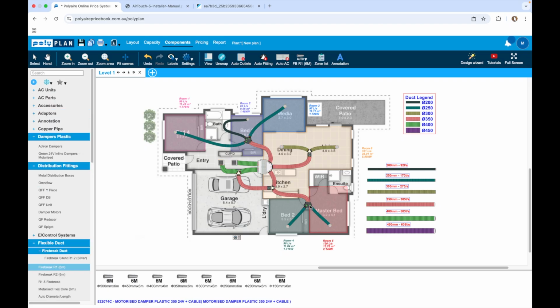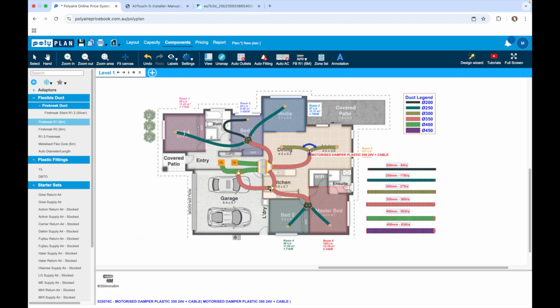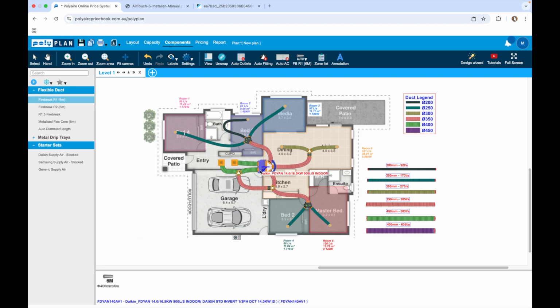But the best thing it does is if I want to sleep in here at 20 and I want to have this at 24 because someone's watching a movie, that will get to 20, that will get to 24. This will start opening, it will bleed its cold air off through here, back through this return air path, and force this unit to stop.